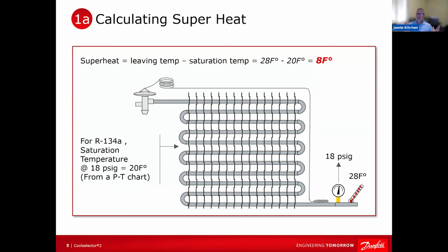The issue is vapor does not really pick up any heat. 99 or 95% or whatever of the heat absorbed in your evaporator is by the liquid. So you want to make sure you have just enough liquid, not too much, not too little, kind of like the Goldilocks zone, right? Because remember, an evaporator is not static. Your humidity increases. You throw a bunch of stuff in there. You open the door. You stare in there, not knowing what you want. All of these things can suddenly throw a load or change your airflow on your coil. If you're right on the corner of having liquid leaving and you suddenly drop your heat load by 5 or 8%, now you've got a river or whatever of liquid heading to your compressor. Nobody wants that, right? So that's where your TXV, being an adaptable control, comes into play.